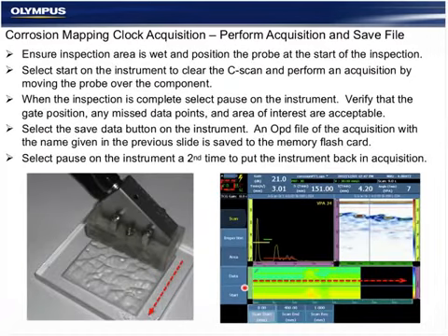And as you can see, we can adjust both the speed and total size of the C-scan regarding how many data points we will accumulate by adjusting the step resolution, or the PRF, and the total size of the C-scan. The bigger number you put in here, the more data points will be saved. Only the visible part of the C-scan, not the buffered part that's not visible, is retained in the clock data file.